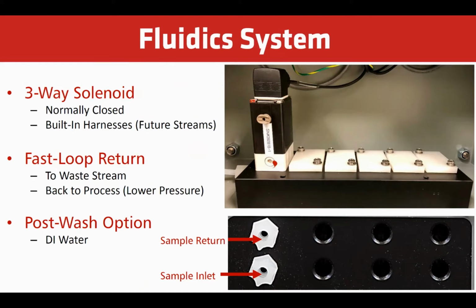So it's always, when it calls time for analysis, the solenoid energizes, the valve opens, and now the sample inlet stops going out the return, goes into the analyzer, fills and drains and cleans the sample cup, and then holds a volume, a known volume, and the analysis starts.